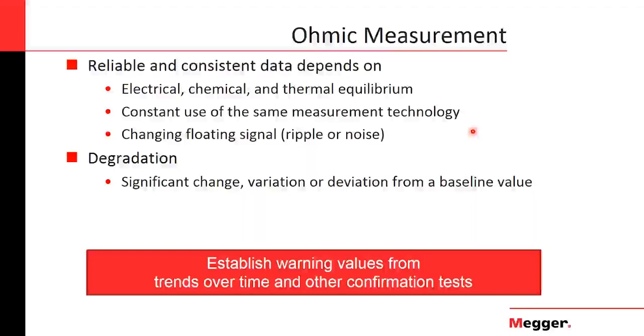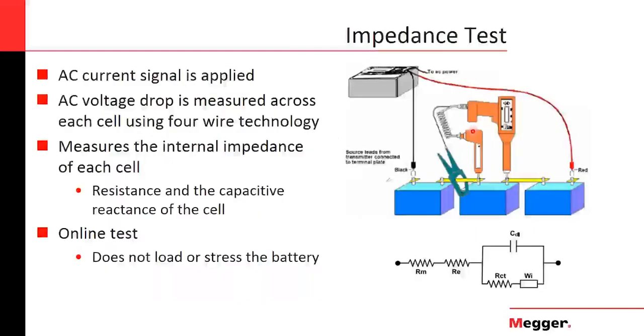And changes in the floating signal, like increasing current or even a ripple current or noise in the system, will also influence the result. Once you have verified that you don't have any of these issues in your measurement, and you obtain a value, you can determine that there's a degradation when there's a significant change, a variation or a deviation from a baseline value. And of course, you need some warning or some criteria to define what is a high or significant change. So these values are established with the trends that you perform by measuring the same cell through time every 6 months. After probably 3 measurements, you can start establishing which are going to be your warning limits. We're going to talk about some recommendations about that as well.